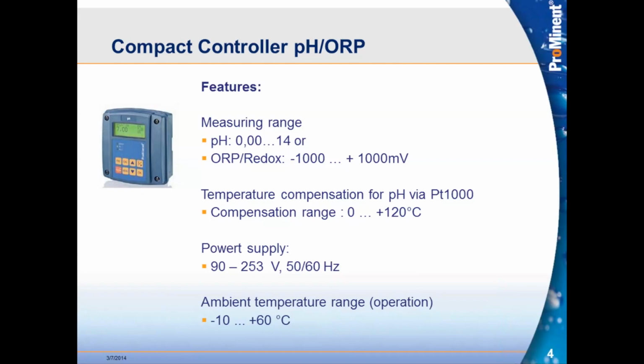So that compensation range is 0 to positive 120 degrees C. Of course, above 100 degrees C we wouldn't have liquid if we're in a water stream anyway, so be very cautious there. That might exceed the range at which that pH sensor or the ORP sensor can operate by itself. But we have a very wide temperature range for that PT1000.